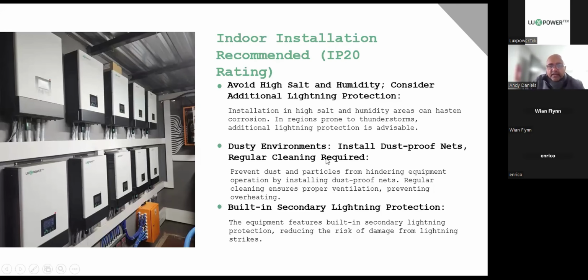dust. And then one of the things that we highly recommend, especially for you guys up there in Johannesburg, where you have a high incidence of weather like lightning and even convection lightning, you have to install SPDs or surge protection devices before the machine. So here you can see that it says we have built-in secondary lightning protection inside the machine, but that's not your... This doesn't mean that you can eliminate it from your installation.